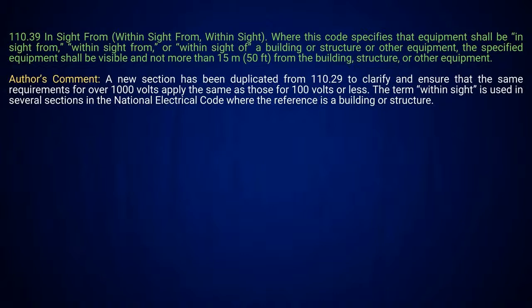Right. Then this is actually a really good one here, because this is where you're going to get over 1,000 volts. They're basically taking the exact same thing that's over in 110.29, moving it over to 110.39, and they're telling you if it's over 1,000 volts, you're basically applying the same requirements. It has to be visible and within 50 feet. So in other words, it has to be in sight from. Okay. Yeah, same requirement.